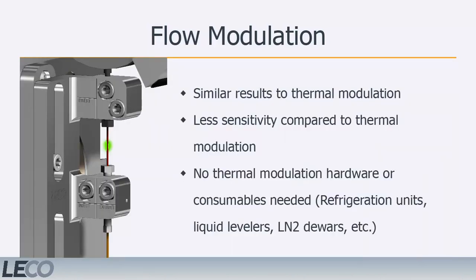Flow modulation produces very similar results as thermal modulation with one major drawback. When a GC×GC system is utilizing a flow modulator, there is a loss in sensitivity because part of the effluent is diverted away from the secondary column. However, if sensitivity is not of primary concern for your application, flow modulation systems offer the benefits of GC×GC separation without the added complexity and cost associated with the consumables required for thermal modulation hardware.